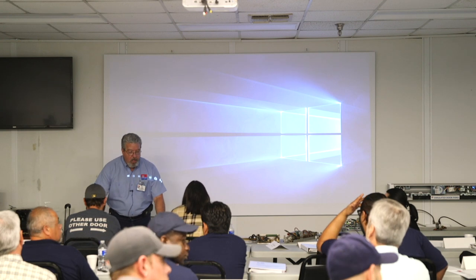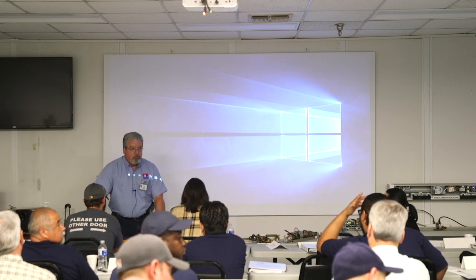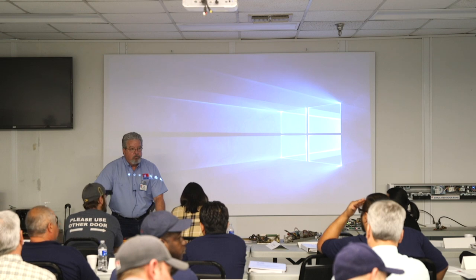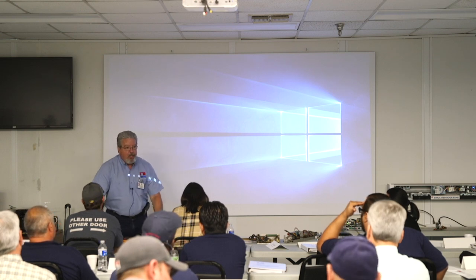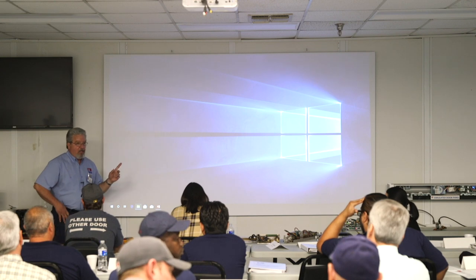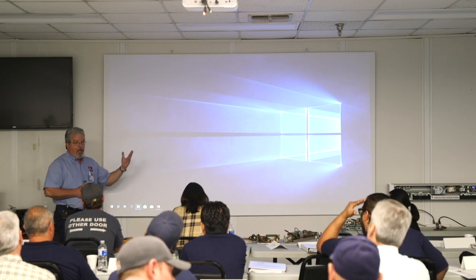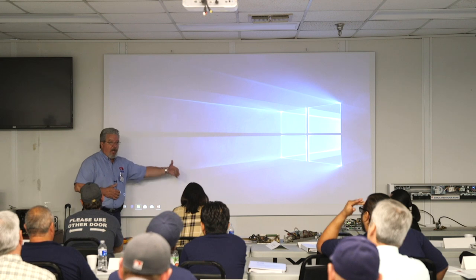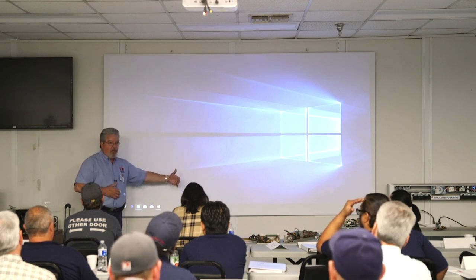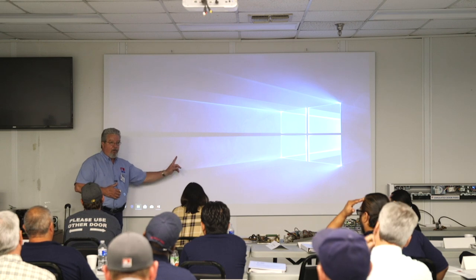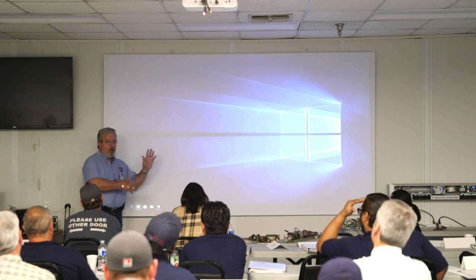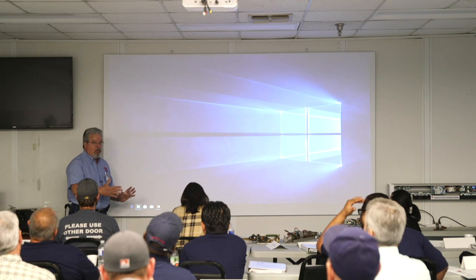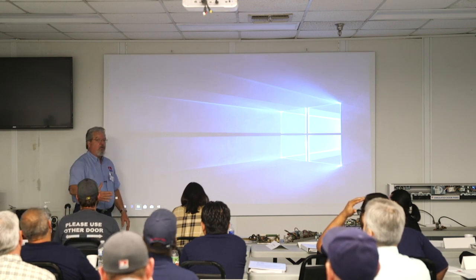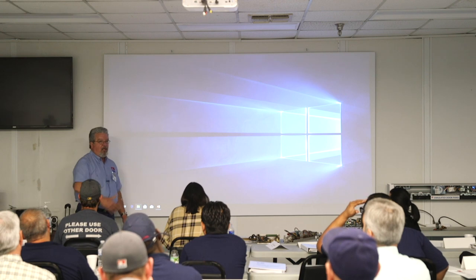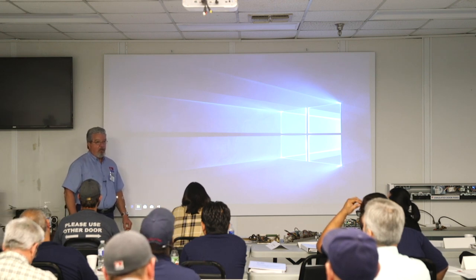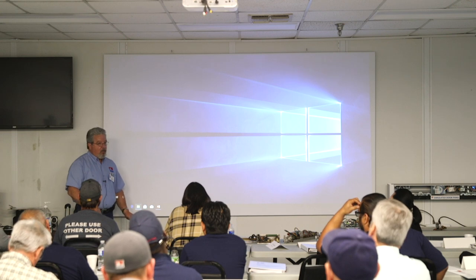John, I've got a quick question. Uh-huh. On that example, you said where the activation zone was on one side and the safety zone was on the other. That's a one-way door. That particular slide was a one-way door, yes. And then if it would have been a two-way door, then there would have been an additional activation zone beyond the safety zone to have the door open before the pedestrian got into the safety zone. That also requires longer guide rails to help channel these people so that they actually go through that secondary activation zone before they get into the safety zone on a two-way traffic swing door. But a two-way traffic swing door is kind of a no-no.